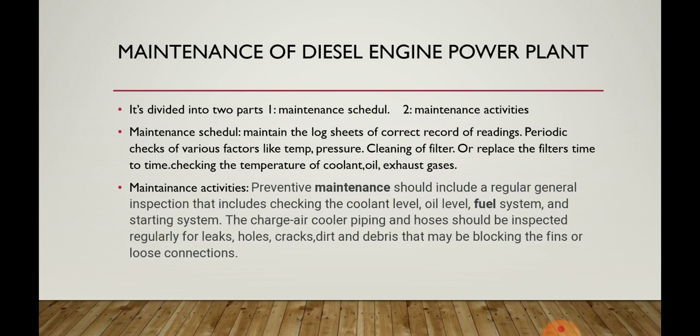The next one is the maintenance of the diesel engine power plant. It is divided into two topics, that is the maintenance schedule and the maintenance activities. The maintenance schedule includes maintaining the log sheet with correct records of readings, periodic checks of various factors like temperature and pressure, cleaning the filters or replacing the filter from time to time, and checking the temperature of the coolants, oil or various exhaust gases. This includes all of the scheduled maintenance.